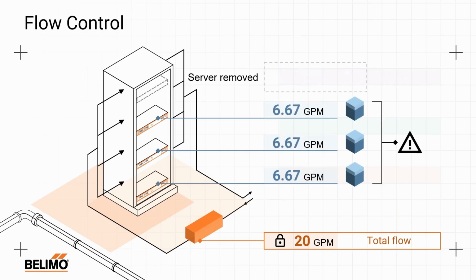Well, essentially that extra 5 gallons a minute is redistributed to the other 3 sets of cold plates on the remaining servers. This is not what we would want to happen, because now we have an overflow on those 3 circuits. Even though the valve is still flowing the right amount, we're overflowing the remaining circuits. What's the jeopardy of that? Well, we want to make sure we don't overflow our cold plates in the long term. There can be some issues surrounding erosion or breakdown of the cold plate materials. They're designed at very specific flow rates, and so it's fairly important that we stay at them.